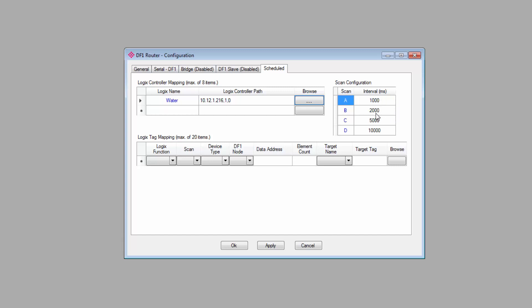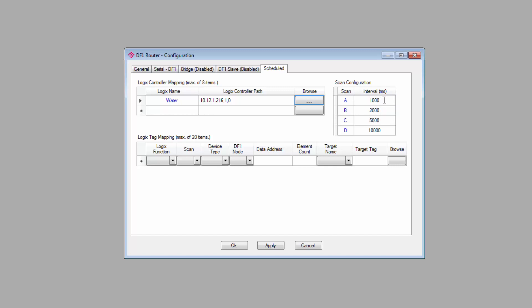As you can see, there are four scan intervals, each of which is configurable. When we get to the mapping portion below, you can assign what scan interval you want to use. So for crucial data, you can refresh the data more frequently, and for less crucial data, or for things that change slowly, you can set a slower scan rate.